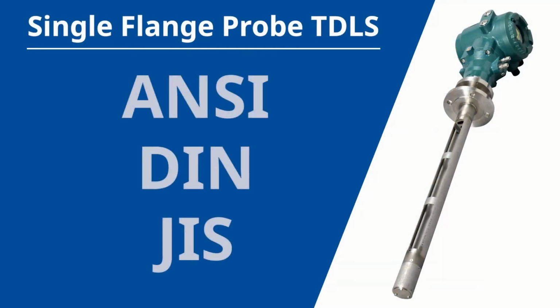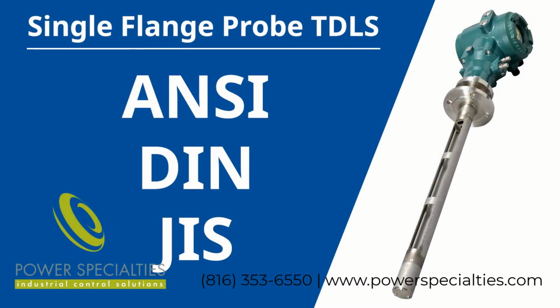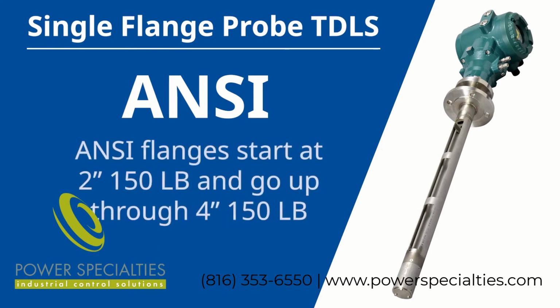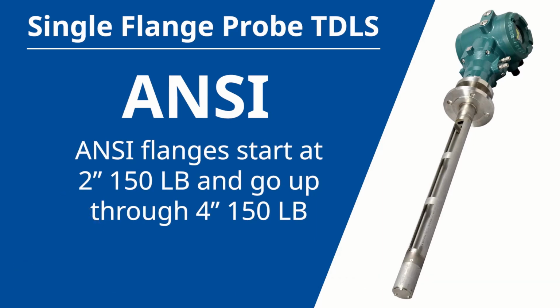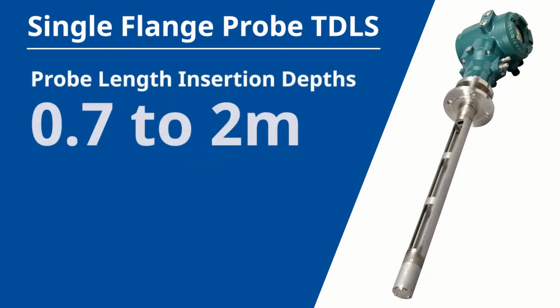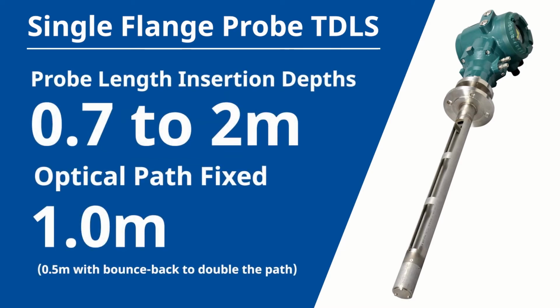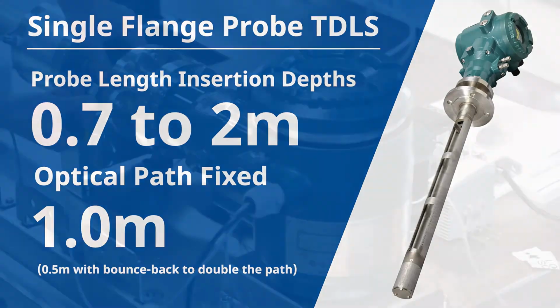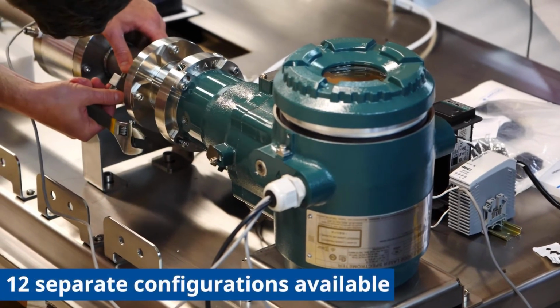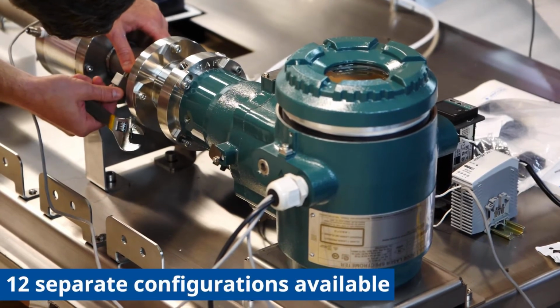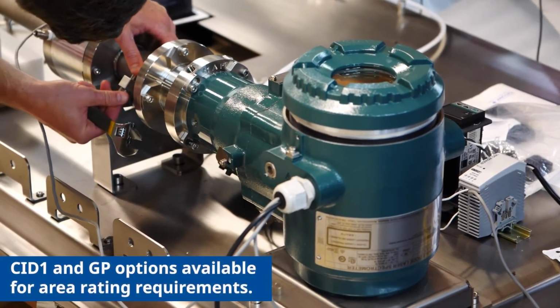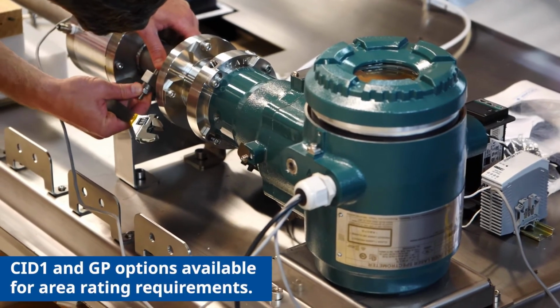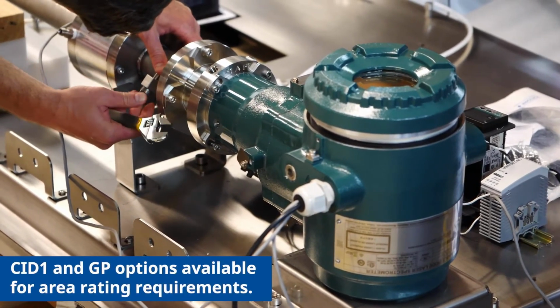The single-flange probe TDLS was built to accommodate a variety of standard ANSI, DIN, and JIS process flanges. ANSI flanges start at 2-inch 150 pound and go up through 4-inch 150 pound. Contact us if you have any alternative flange needs like 300 pound flanges. The probe lengths have variable insertion depths from 0.7 to 2 meters. The optical path is fixed at 1 meter, half a meter with bounce back to double the path. All that changes is the length from the flange to the beginning of the purge interface. Keep in mind which orientation you would like the display and head when ordering, as there are 12 separate configurations available. We also have separate Class 1 Division 1 and general purpose options available for area rating requirements. No alignment is required for probe installation.